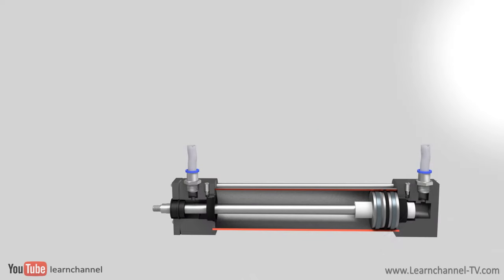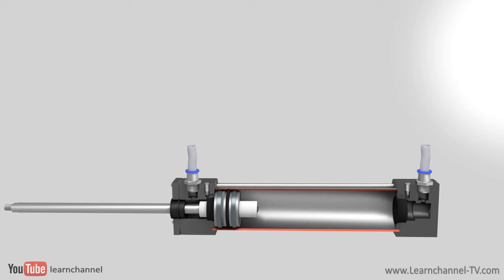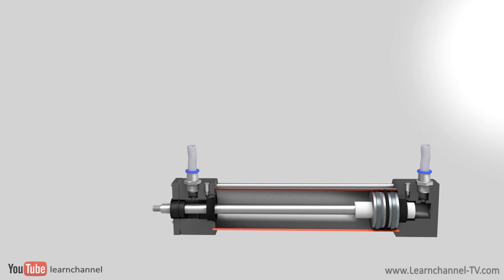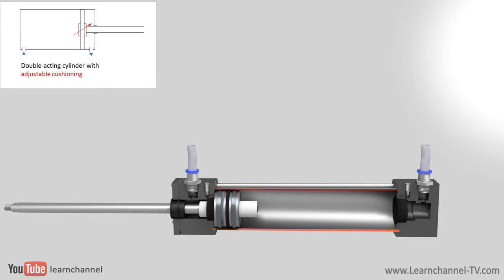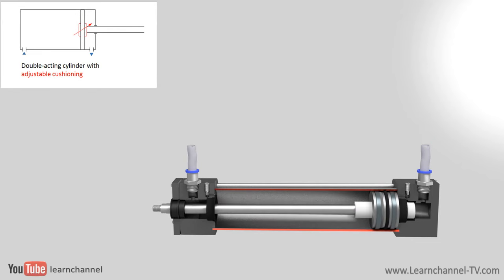When the piston hits the head or end cap, it creates a hard shock. Besides the stress on the cylinder components, it is noisy and transmits vibration to the machine. Cushioning is a possibility to decelerate the piston at the vicinity of the caps to prevent these hard shocks.